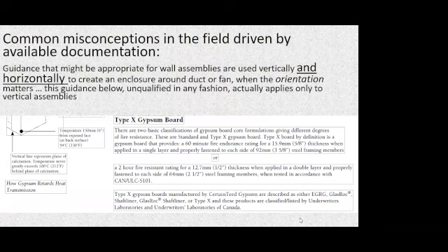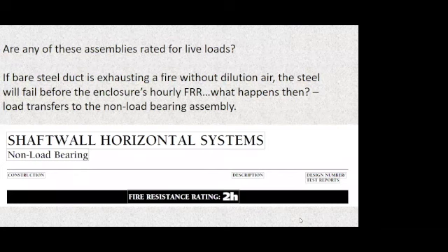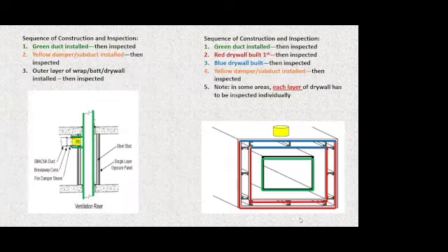And if you think it's just those tables that say that, if you go to the Gypsum Association's design guide, it says the same things. All of the known drywall designs have these limitations. All of the performance tables in the building code say the same thing. And so that's our benchmark for fire rated duct systems. And when you see a fire rated duct system, there's lots of reasons they may have done it, not just to get to that fire resistance. So not just to get to that equivalent fire resistance.